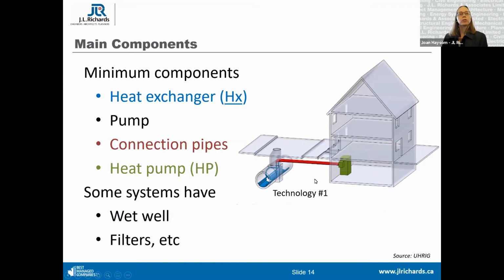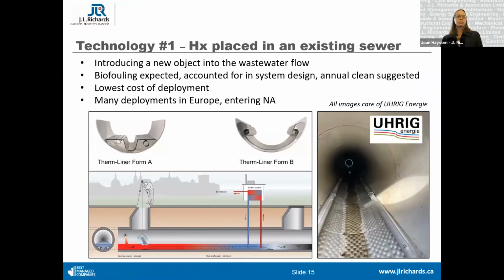This is technology one, which we'll look at in more detail: an actual heat exchanger. I use the short form HX for the heat exchange component that's inserted into an existing sewer line. It sits on the bottom, designed with a ramp at the start, and is held in place through ring clamps. It sits through that sewage at all times. Some biofouling is expected across the surface, and that decrease in heat transfer efficiency is accounted for in the system.